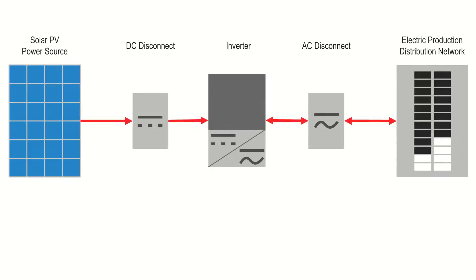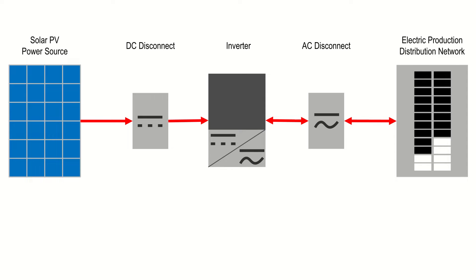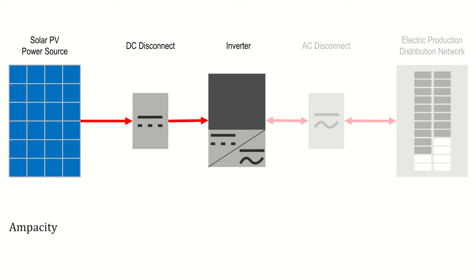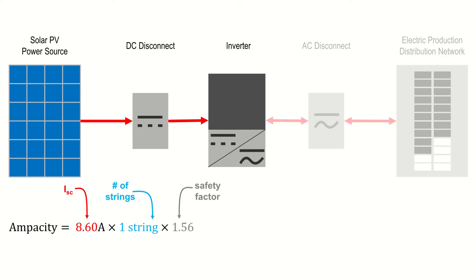In the case of a fusible disconnect, the fuse size that you select will depend on how much current is being carried by each set of conductors coming from the solar array and whether or not you've used a combiner ahead of the disconnect. The circuit ampacity will be based on the maximum electrical current, which when working on the DC side of the circuit is equal to the short circuit current ISC of each string in the array. In this case, we'll multiply the short circuit current ISC times the number of strings in the array times the safety factor of 1.56. The safety factor of 1.56 incorporates two separate factors based on the NEC: one factor to account for the continuous current of a circuit, and another providing a cushion against nuisance trips. You'll then select the closest fuse size at or just above this ampacity value as required by the NEC.